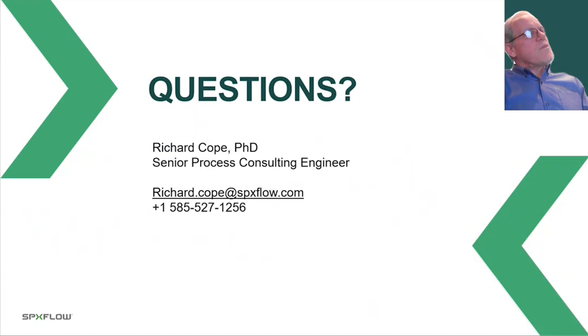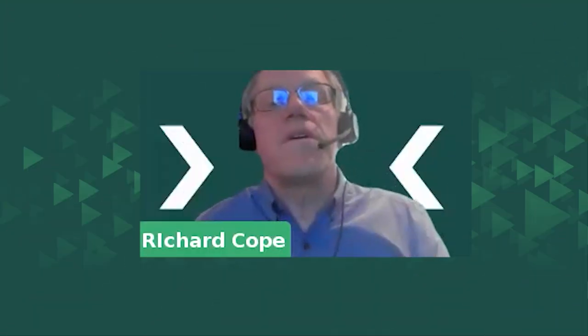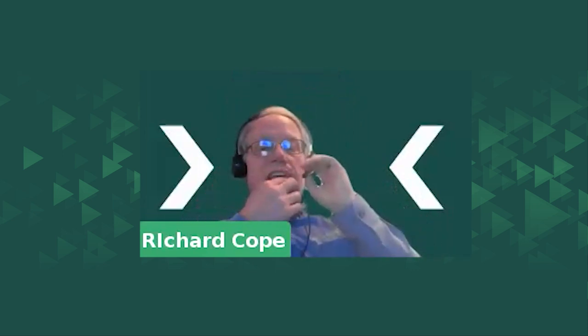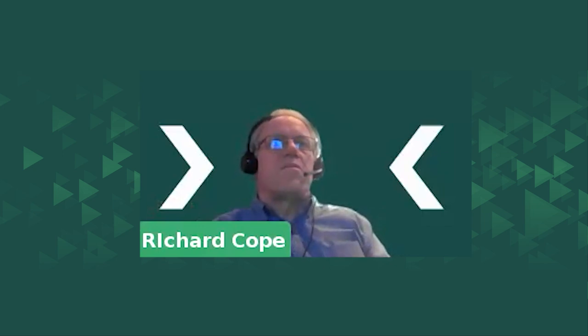Thank you for your time. I would now be happy to answer any questions. A question came in: the correlation shown for convective HTC was for three specific impeller types — was it developed for other impeller types? The correlations are developed for impeller classes, not a specific impeller. So for hydrofoils, any hydrofoil from Lightnin, Philadelphia Mixers, or others would fit. Similarly, disc turbine correlations cover Rushton, CD6, Smith turbine, R130 in Lightnin terminology, etc. The correlations give enough variety of impeller classes to let you decide which best fits your application.